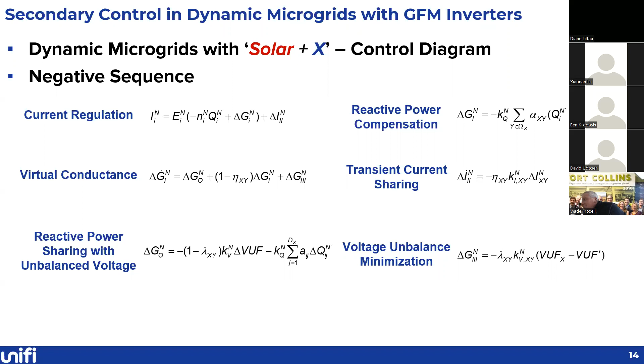Additional functions can also be incorporated into the overall framework. One of these is voltage unbalance mitigation at critical infrastructures or critical buses. To minimize the voltage imbalance, we need to consider some negative sequence control, use negative current regulation, and also leverage virtual conductance built based on the negative sequence model to mitigate the imbalance. That is the negative sequence control functions we designed in the overall control diagram.